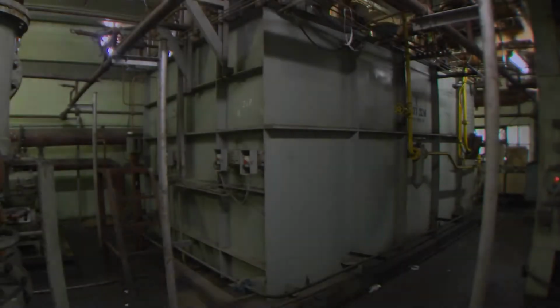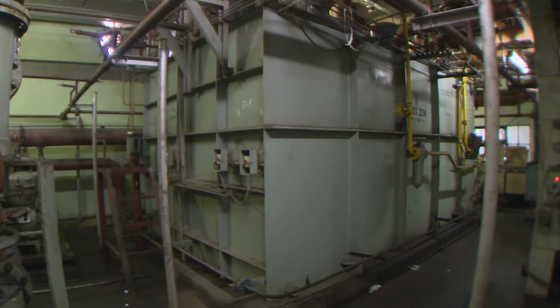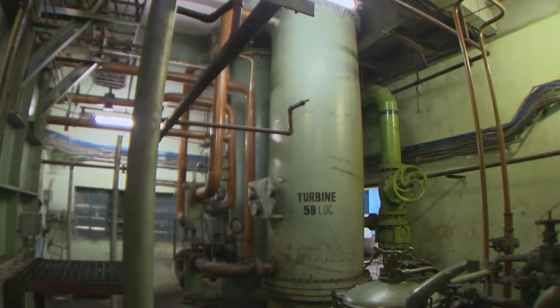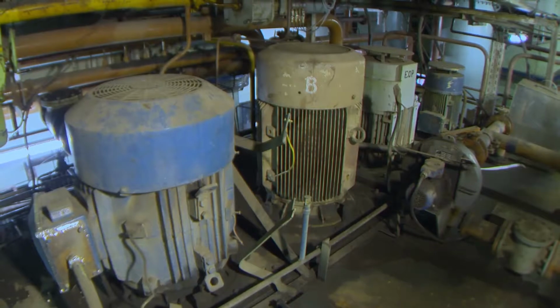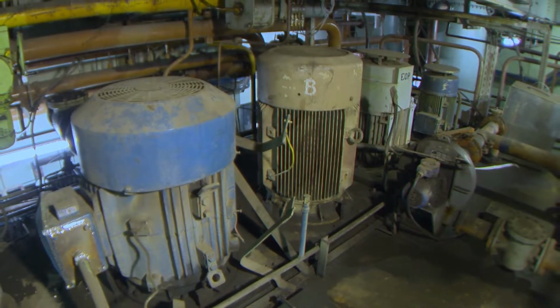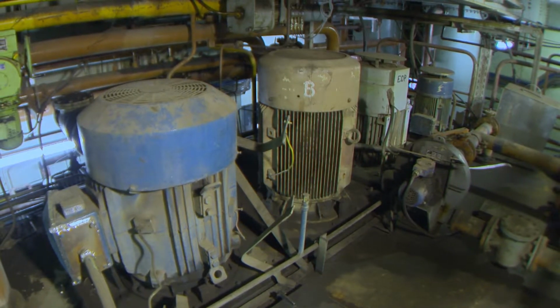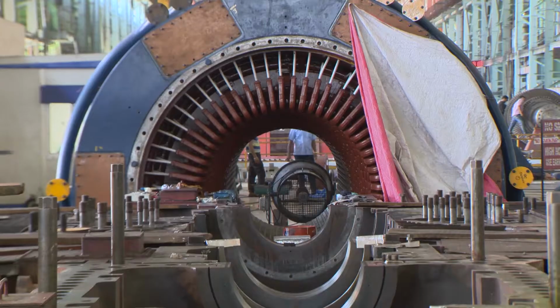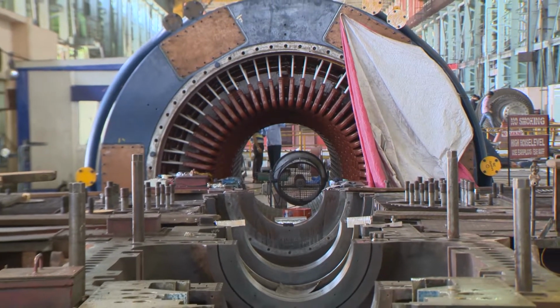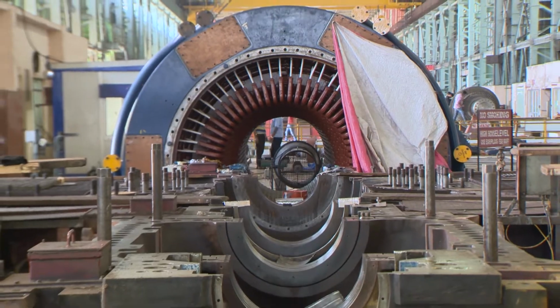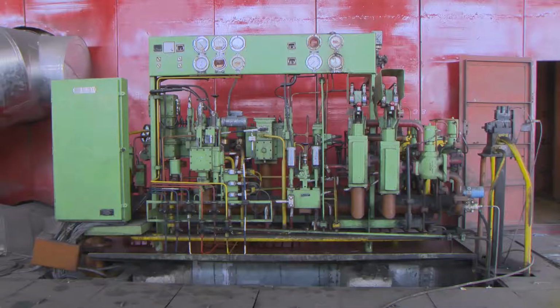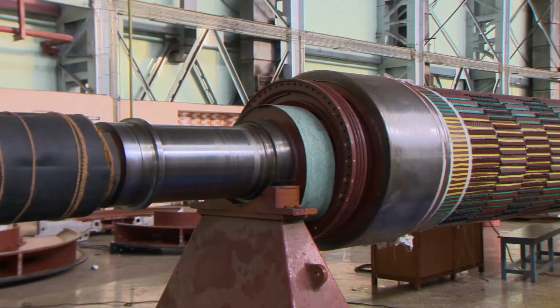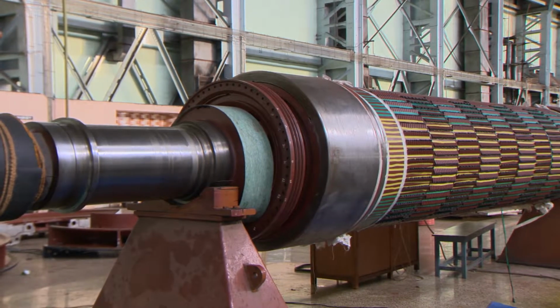Turbine oil system. The turbine oil system consists of one main oil tank along with lube oil coolers, main oil pump, auxiliary oil pump, emergency oil pumps, jack oil pump, etc. It supplies oil to turbo generator bearings, lubrication, LP bypass system, turbine governing system, hydraulic turning gear and jacking oil for the turbo generator rotor.